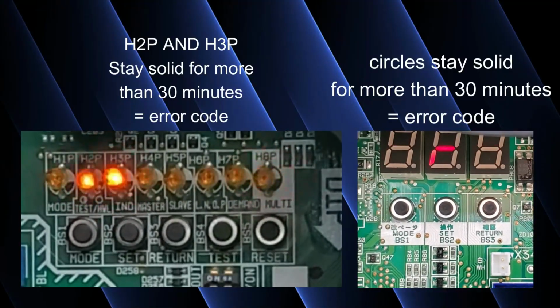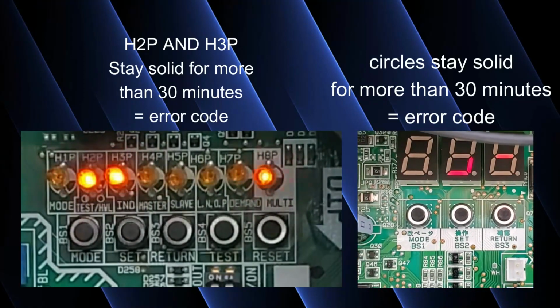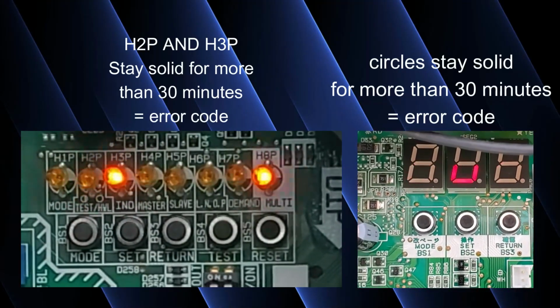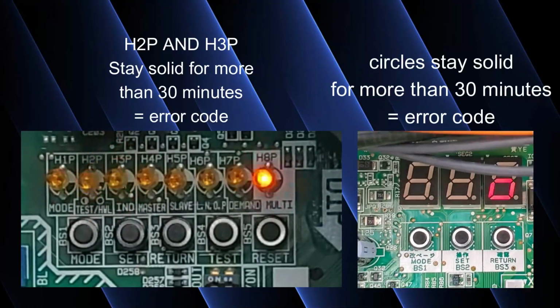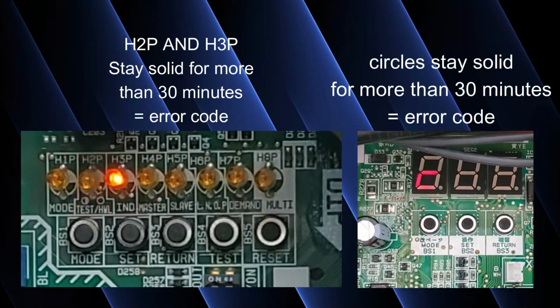Now, at any point in time during this initialization process, if on a newer board you have the 3 small circles go solid and then they stay solid for more than 30 minutes, there is an error code within the system and it failed to initialize. So anytime you get any of these error codes along the way, the outdoor unit fails to initialize, the best thing to do is to go around and turn on all the thermostats, find the error codes, resolve the error codes, and then shut down the outdoor units. Anytime you shut down the outdoor units, leave them off for about 5 minutes so the capacitors can discharge and then power them back up and repeat this power up process.